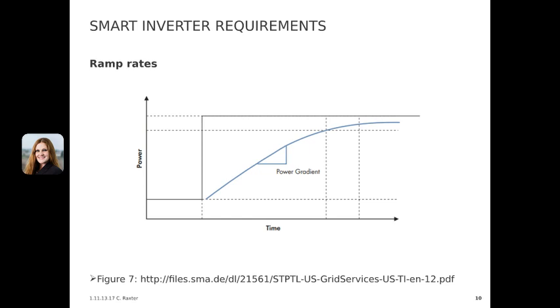And essentially what that means is that a PV inverter, the second that the sun is on the PV modules, can turn on and immediately start producing power. In that instance, the power has to go somewhere, so the utility has to start turning their generators off to compensate for all that additional electrical generation that's being dumped onto the utility grid. And they can't do it that fast. So telling the inverters, no, we know you can go up to 100% immediately, but really we want you to go up incrementally, so you're really only going to start at 60%. It gives the utility more time to actively turn off their generators and help them better manage their loads.